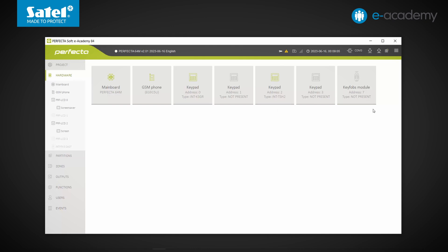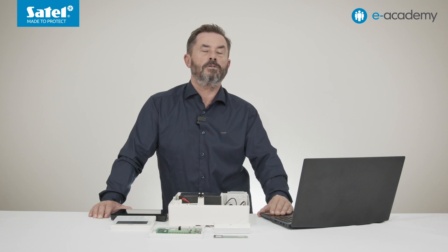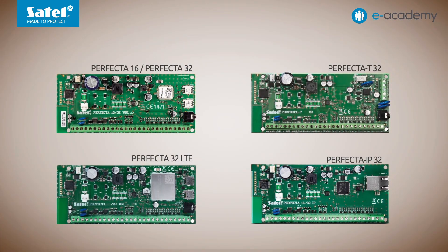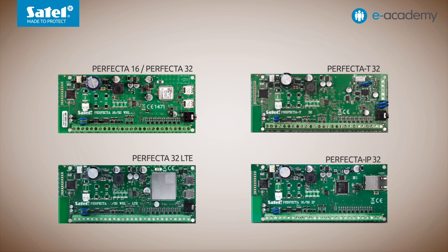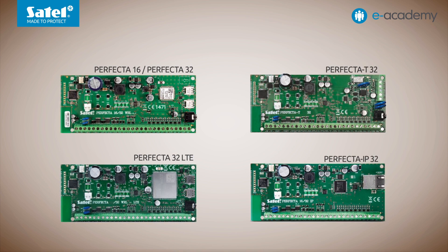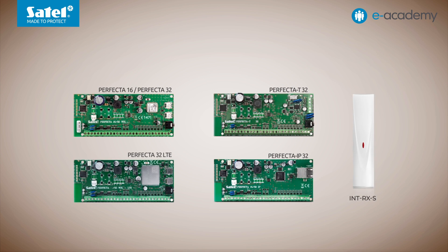At the end of the list is the key fob receiver module. Click on it — the text boxes are empty, which means there is no information about the device because no module is connected or identified. So why are the key fob receiver module settings displayed in the program? This is because the PERFECTA 64M panel by default behaves similarly to the basic PERFECTA panel models without the WRL designation — that is, control panels not equipped by default with a micro module supporting wireless devices. It is to these control panels that the INT-RX-S key fob receiver module can be connected.